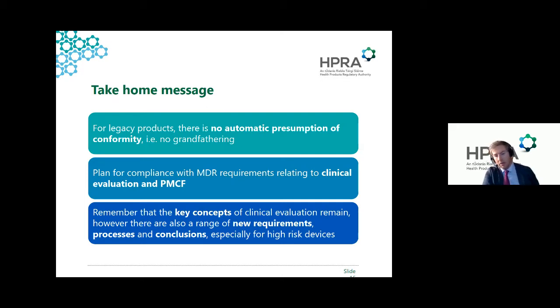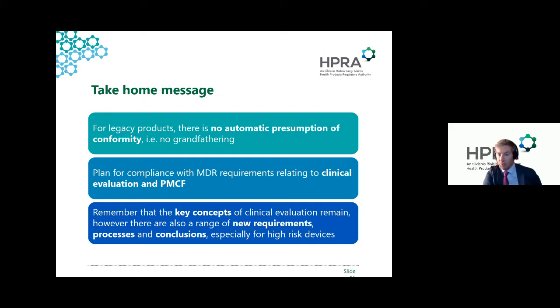Planning for compliance with MDR requirements — especially the clinical requirements in Chapter 6 — means you should review your clinical evaluation to identify any gaps. MDR brings new processes and requirements, including new types of plans. It's important to map these out from a process or quality perspective. If you do have clinical data gaps, looking at how those can be filled through post-market clinical follow-up studies is really important, especially given the short time until the date of application. The key concepts remain, but be aware of new requirements, new processes, and new types of conclusions.